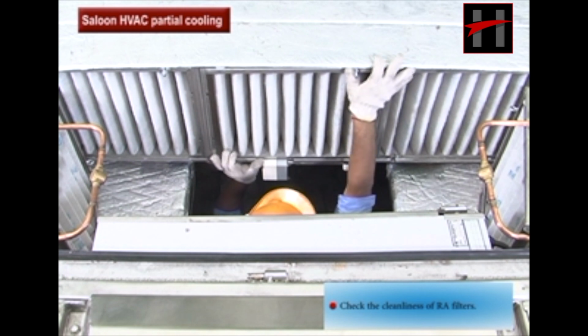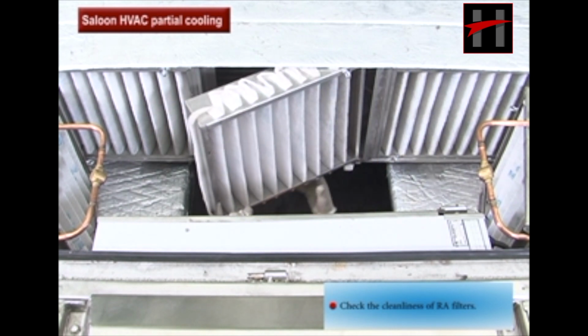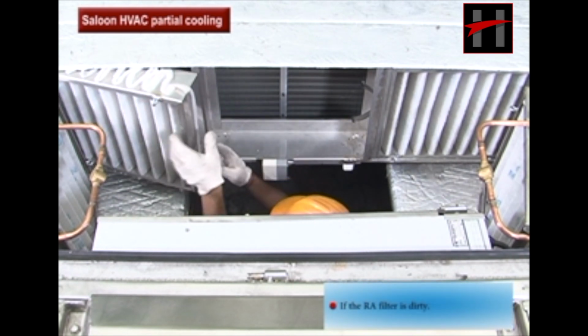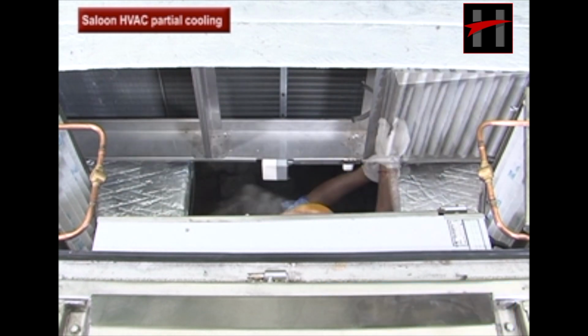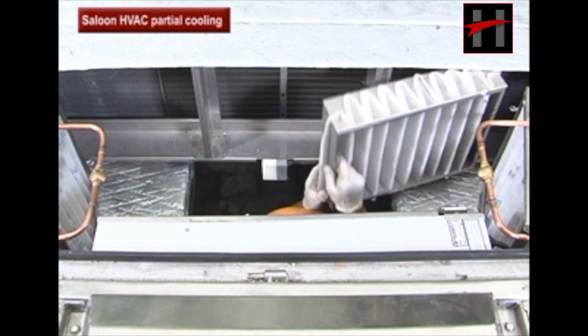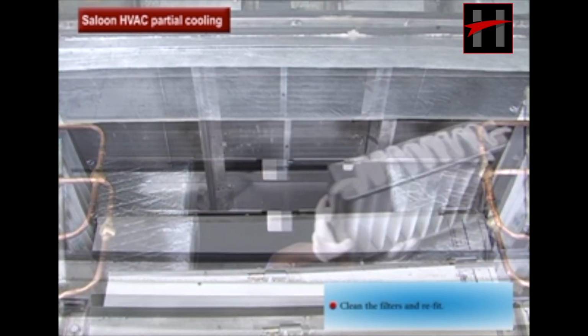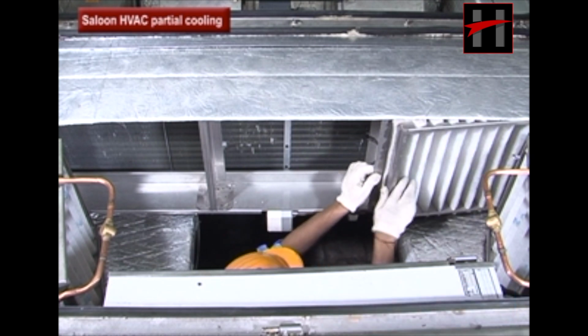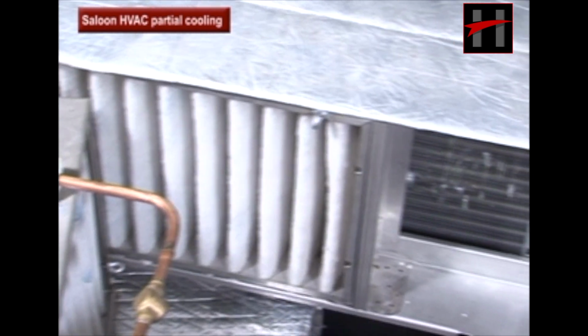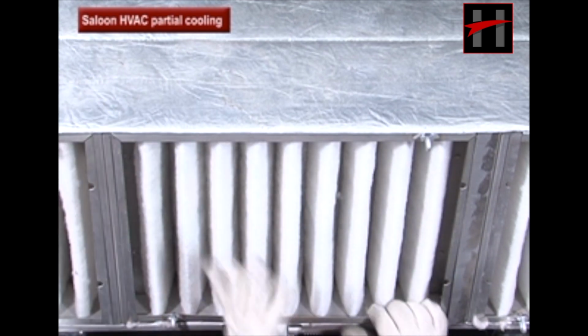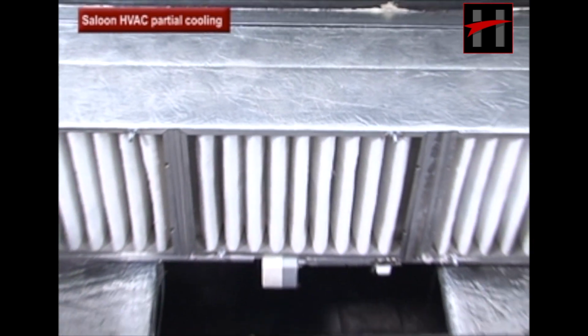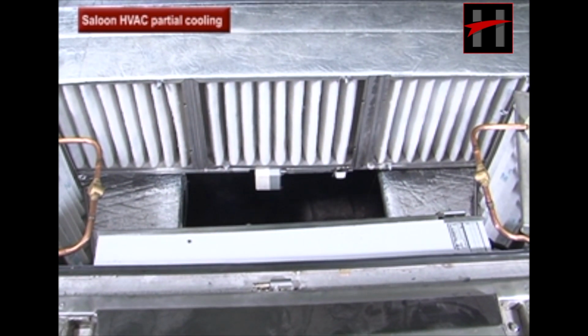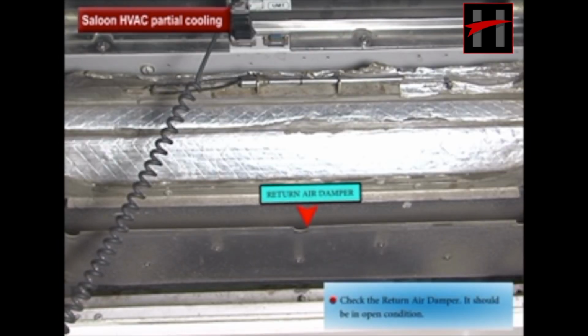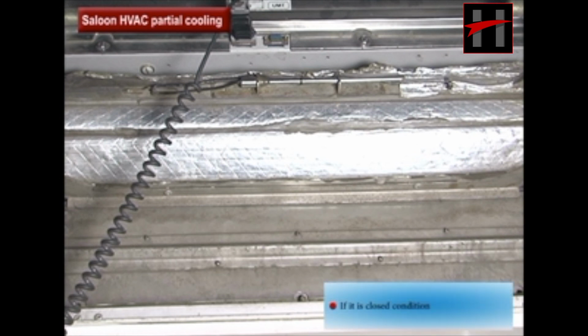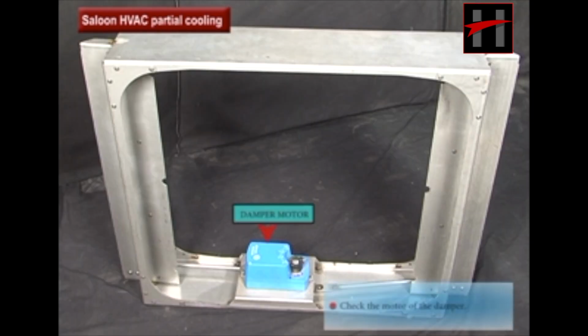Check the cleanliness of the return air filters. If the return air filter is dirty, clean the filters and refit. Check the return air damper. It should be in open condition. If it is in closed condition, check the motor of the damper.